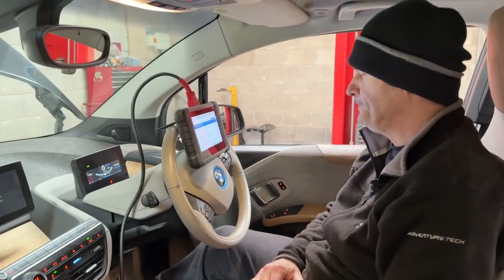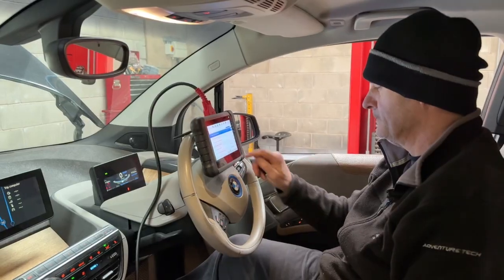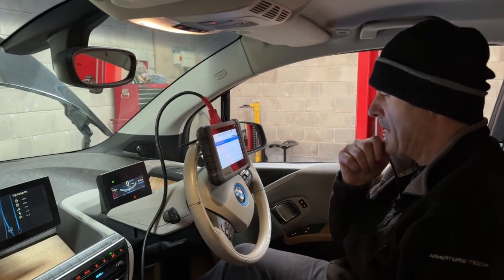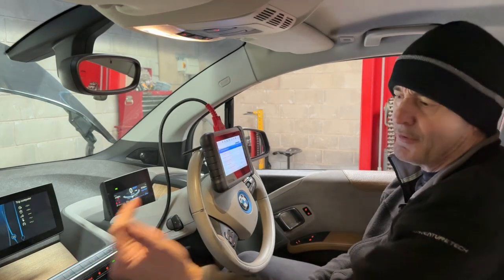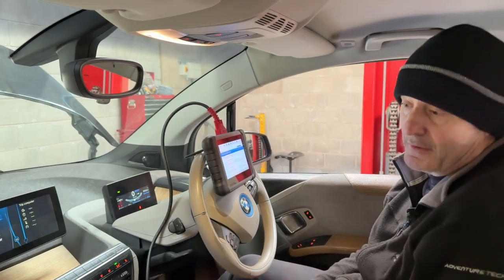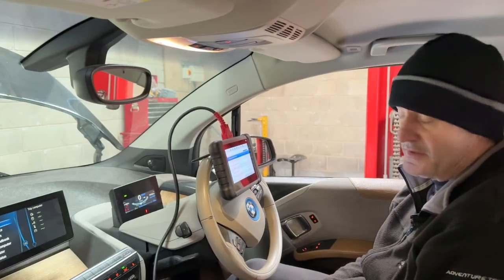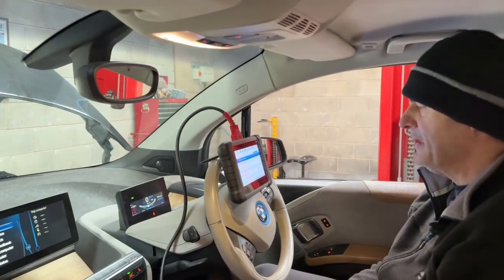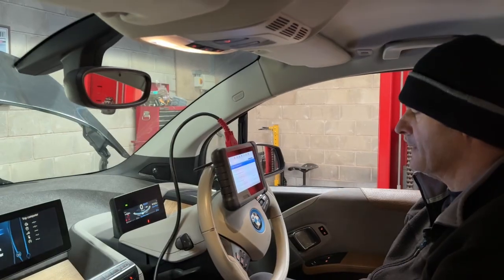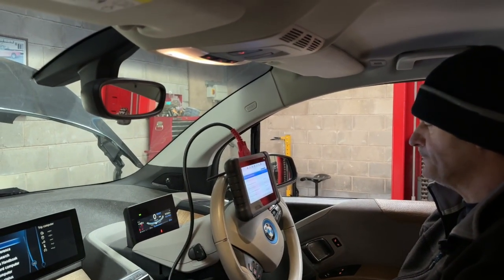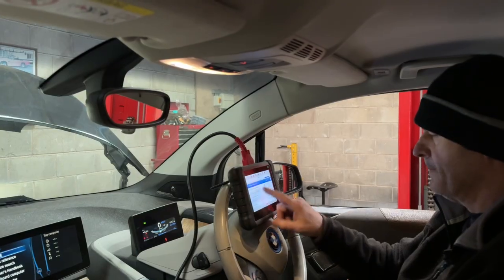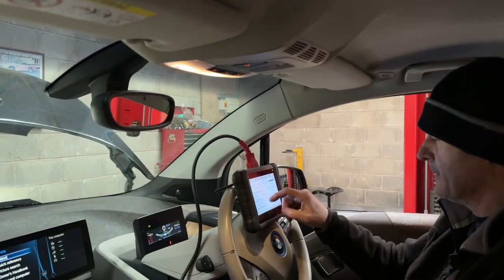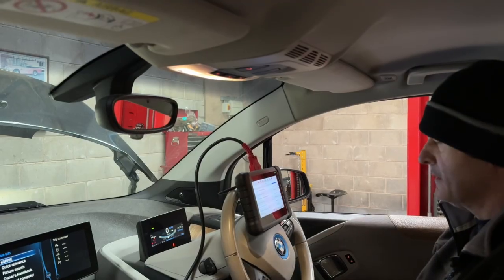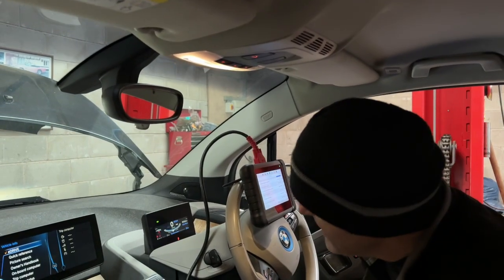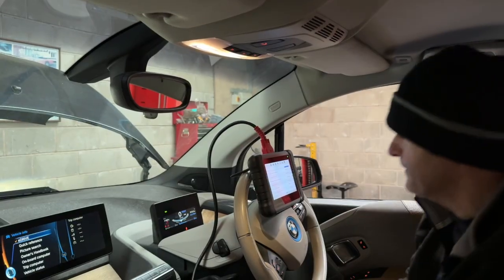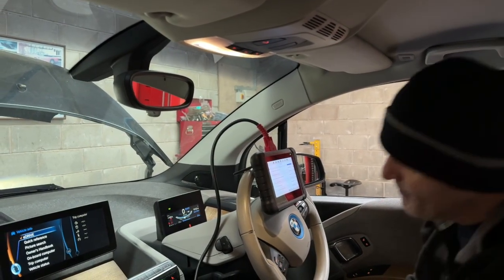So whatever we did caused it to unilaterally isolate the high voltage system. Well, we took all three of the relays out of that box from underneath the glove box, and that seemed to cause it to be less than happy. Yes, so we've done a hard isolation by disconnecting the high voltage isolator at the front, and then simply reconnecting it, and now it's happier. And now it's telling me there are no faults. No faults at all. Yep.